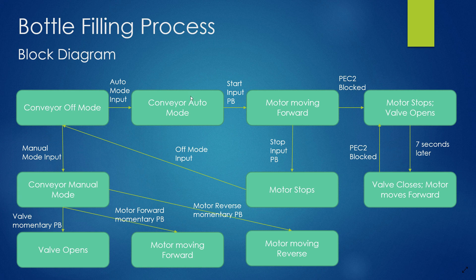And when we put it to auto mode, we need to hit the start button. Once we hit the start button, motor moves forward. When the middle photo eye is blocked, motor stops, valve opens.